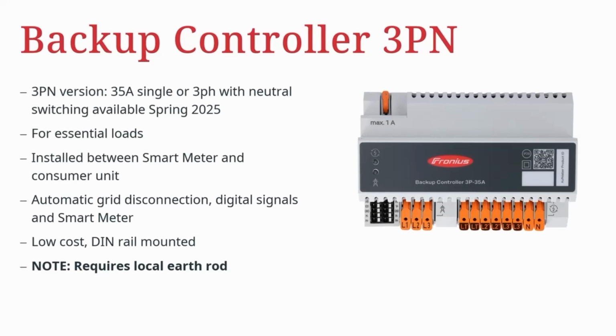If the meter dies, the inverter understands that we may be in a grid failed mode. It will also measure for the voltage from the grid, and if it's able to determine that those essential settings are not available, it will switch into the backup mode. When the grid is re-established, the meter becomes live again. The device is able to then switch back to the grid connection mode and the inverter will reset.